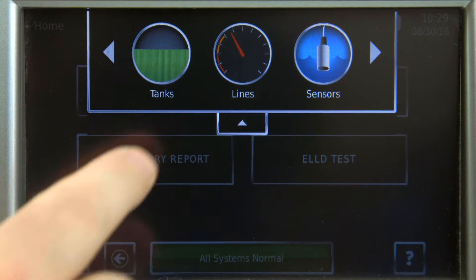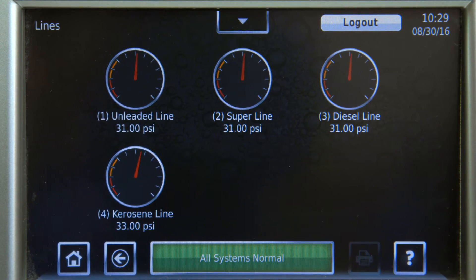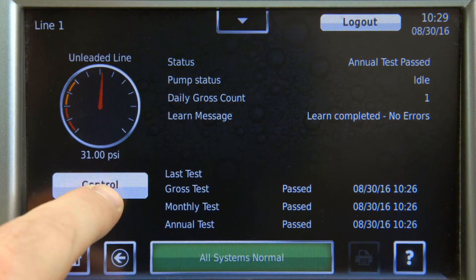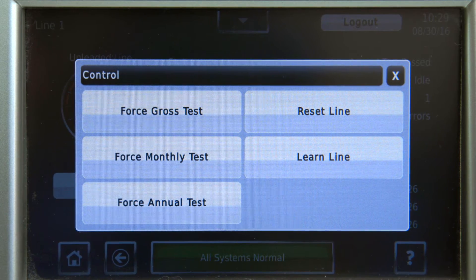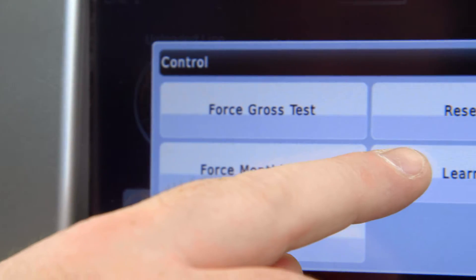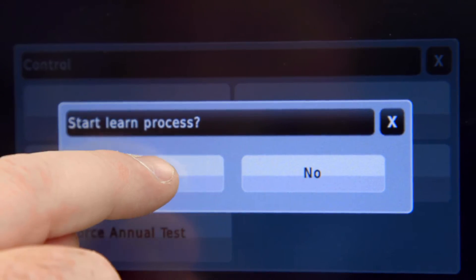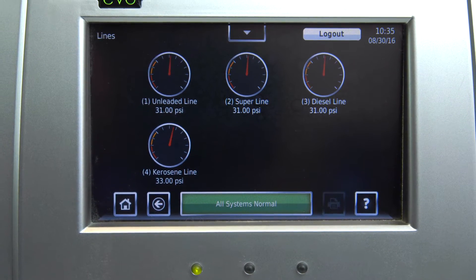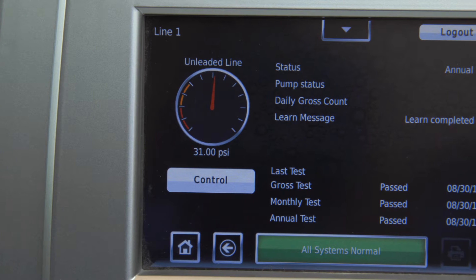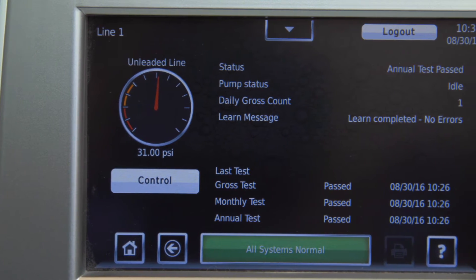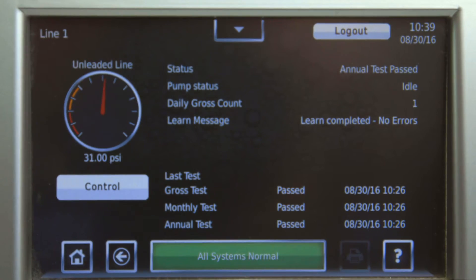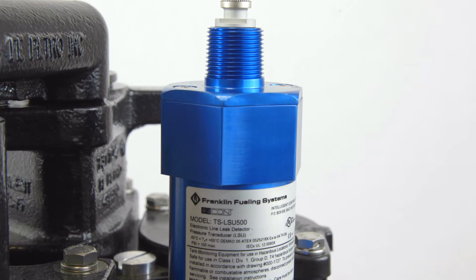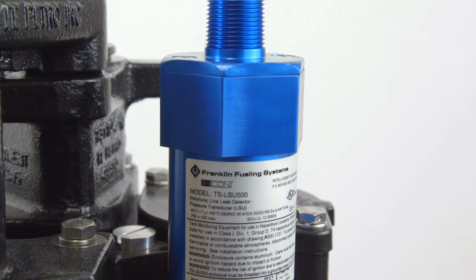Statistical line leak detection allows us to take pressure readings throughout the day in between dispenses and statistically evaluate that data to determine if there's a leak. This becomes critical for sites that are very busy with very little downtime — the more fuel they dispense, the less time there is for leak detection software and equipment to do their job. The ability to do statistical leak detection is huge at busy sites.